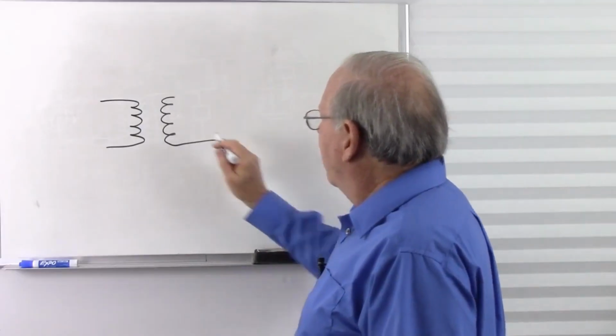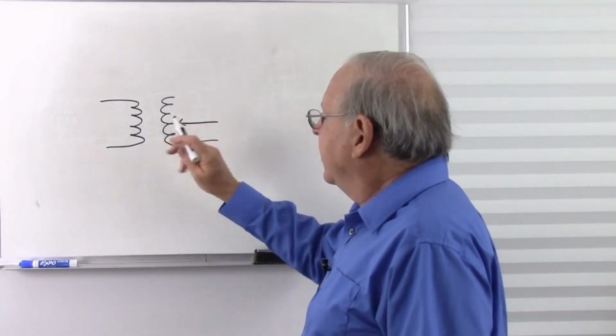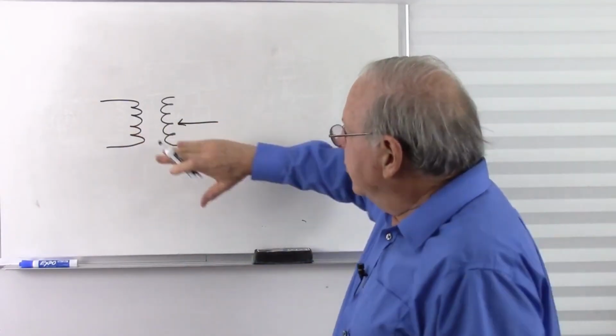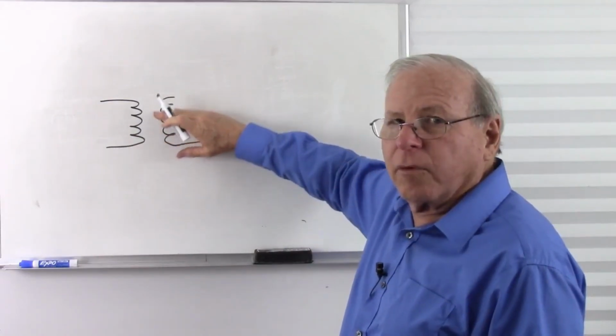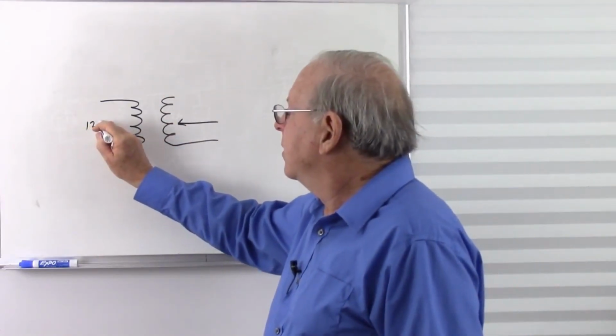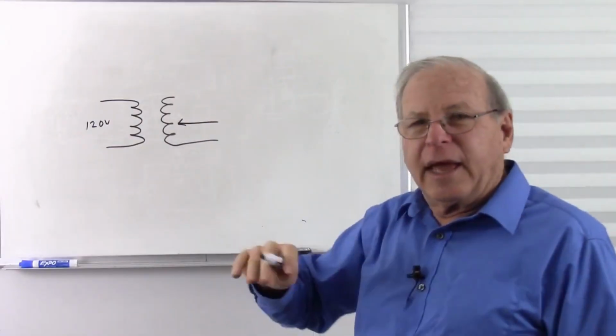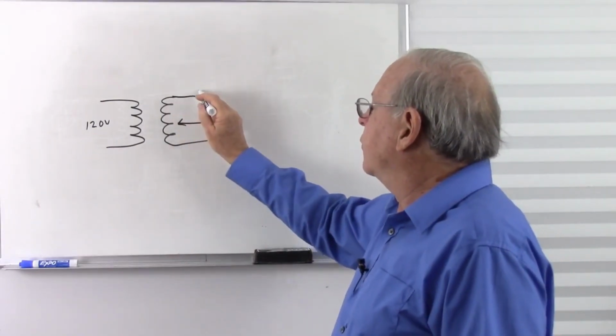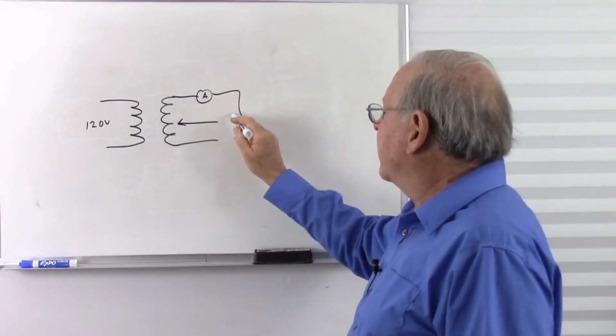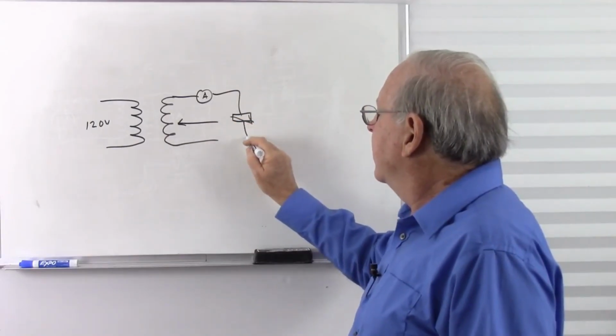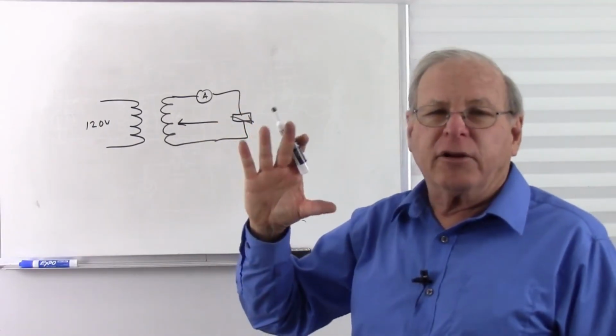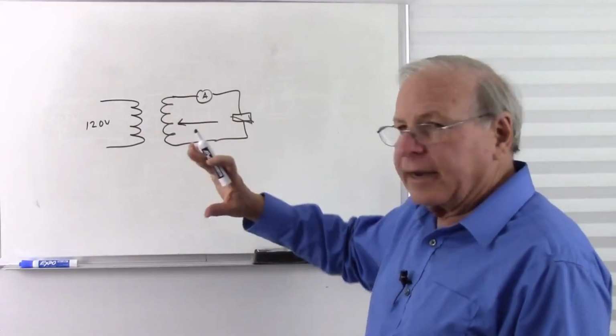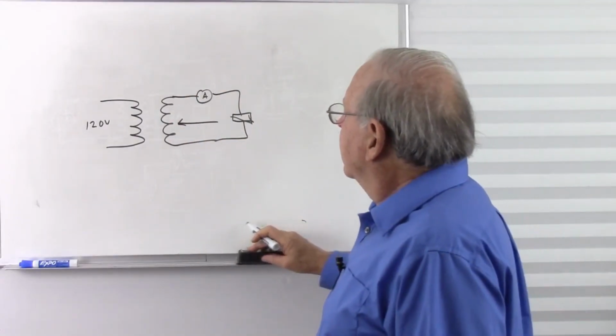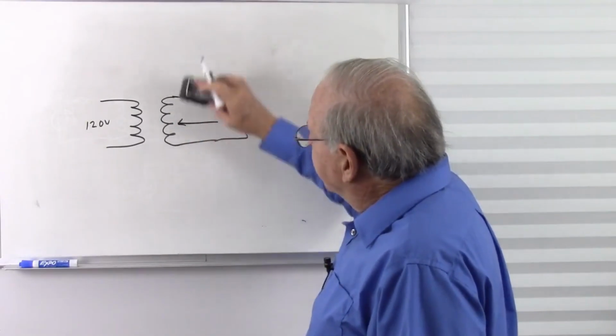So the secondary coil had a wiper on it, so we could turn a knob and it would go from 0 volts all the way up to 120. And as I turned that up, we would have that go through a current meter to our device being tested. And if I saw that current going up, I knew there was a problem, crank it back down and start troubleshooting. So that was a variable.